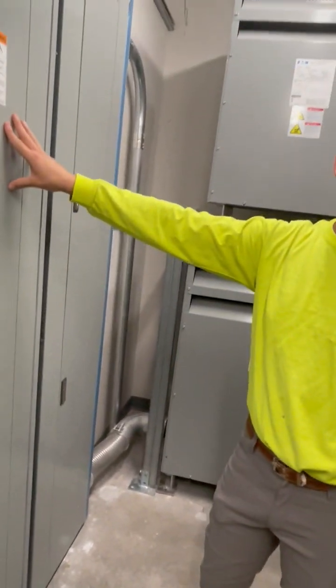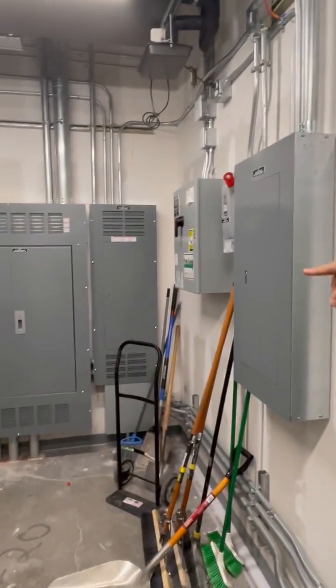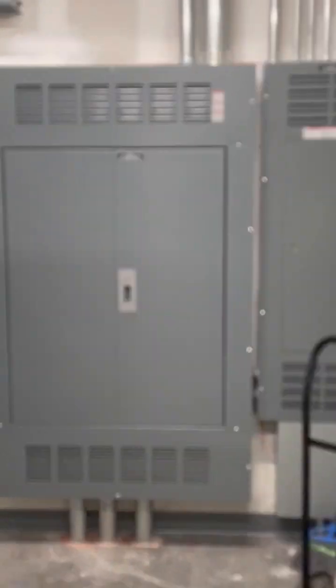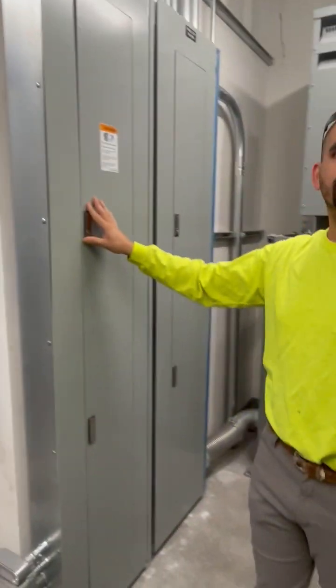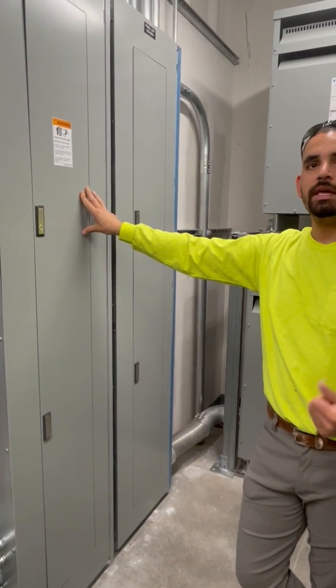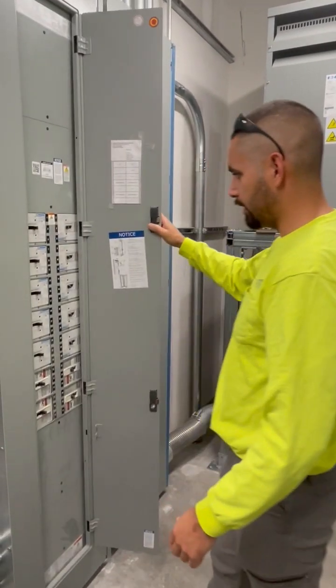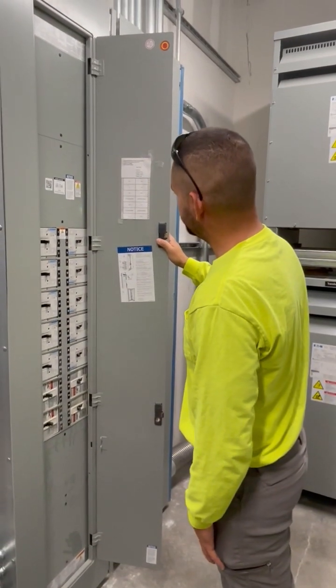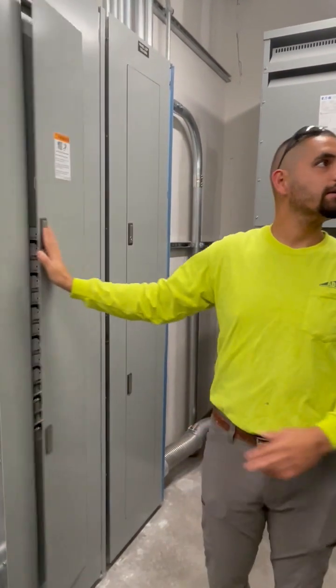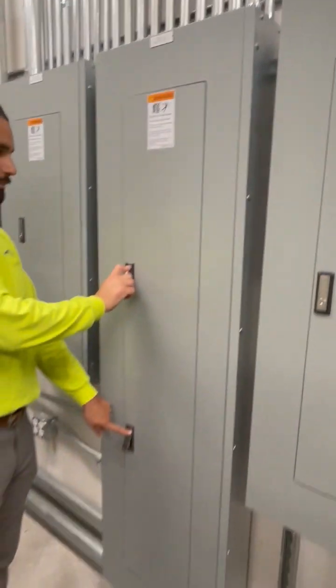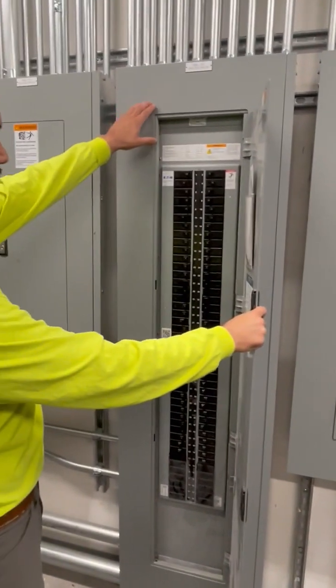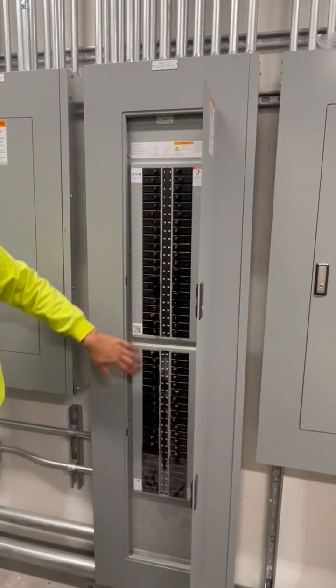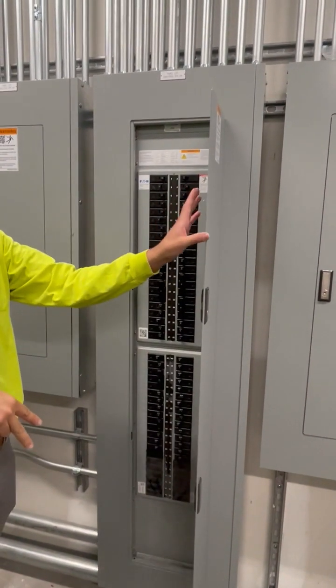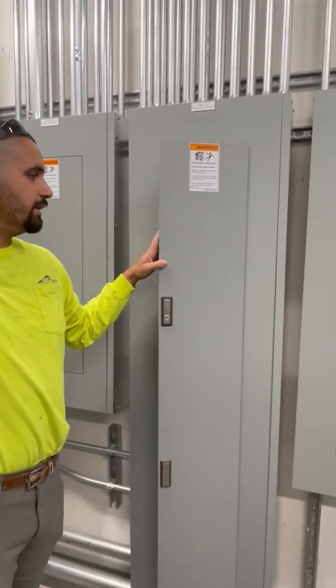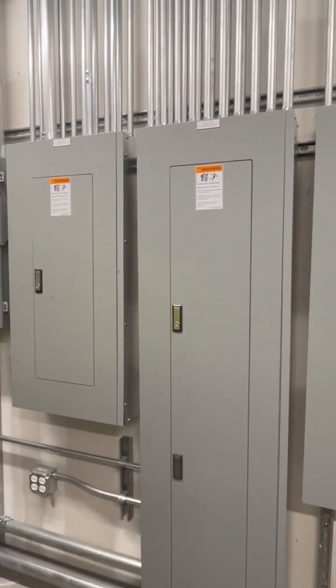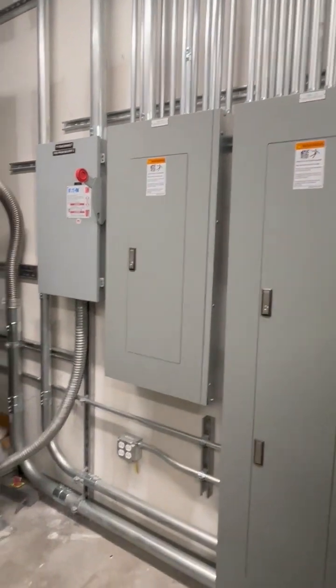This is a high voltage panel. This comes from the panel HDP that's landlord provided. Okay. This basically feeds all your high voltage power like AC units, heat pumps. You have the water heater in here, the DX units on the roof. The freezers, which is the big one, are being fed off of this panel, LP2. There's a 3-pole 40 amp breakers. This feeds the freezers on the second floor and the 2 on the first floor. It feeds the units that are on the roof. Okay. I guess that'll be it for here.